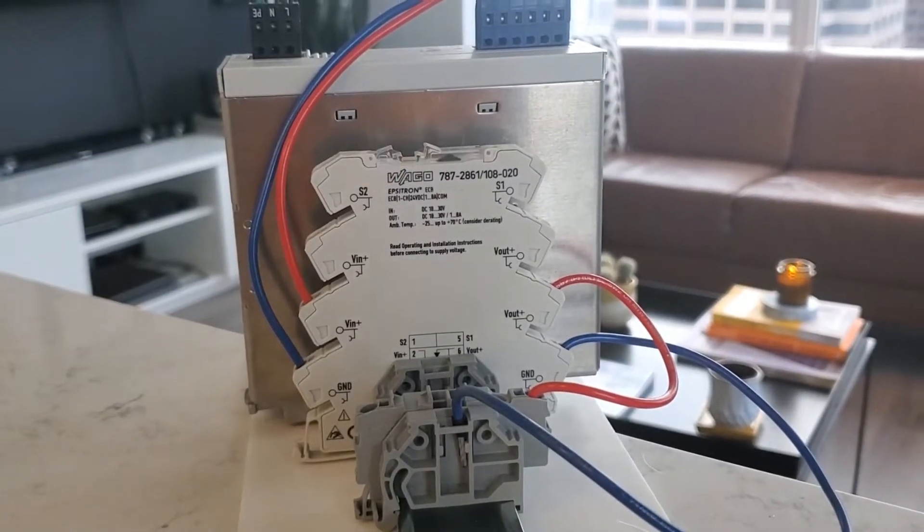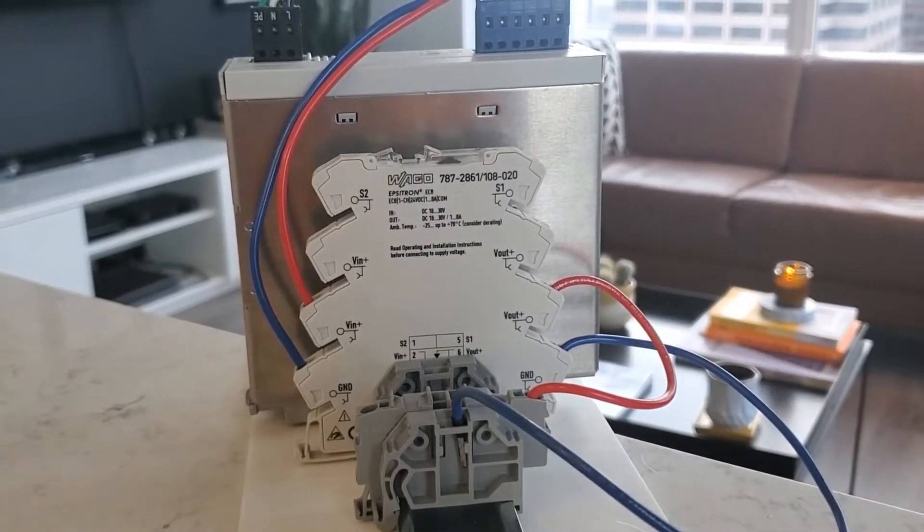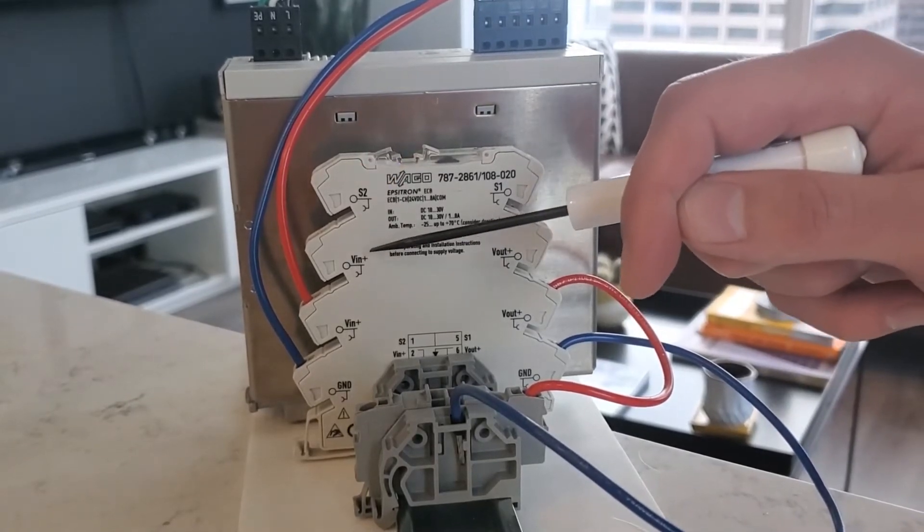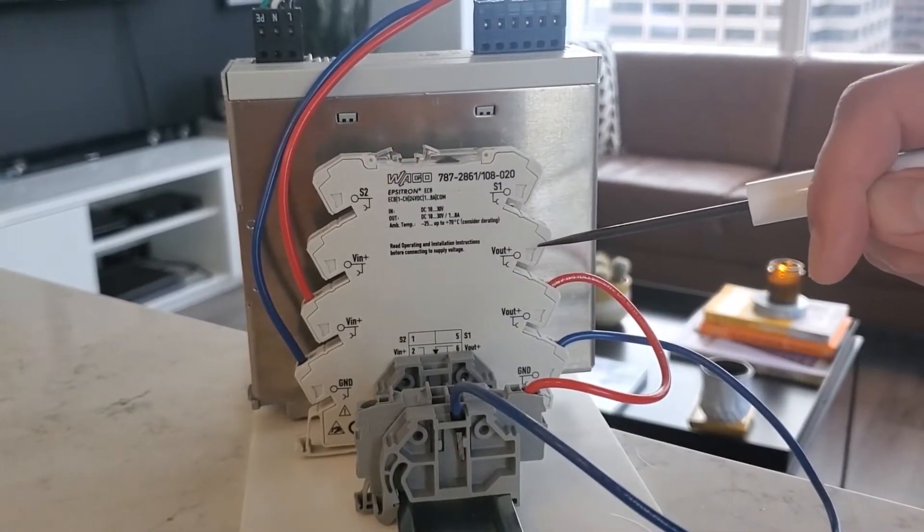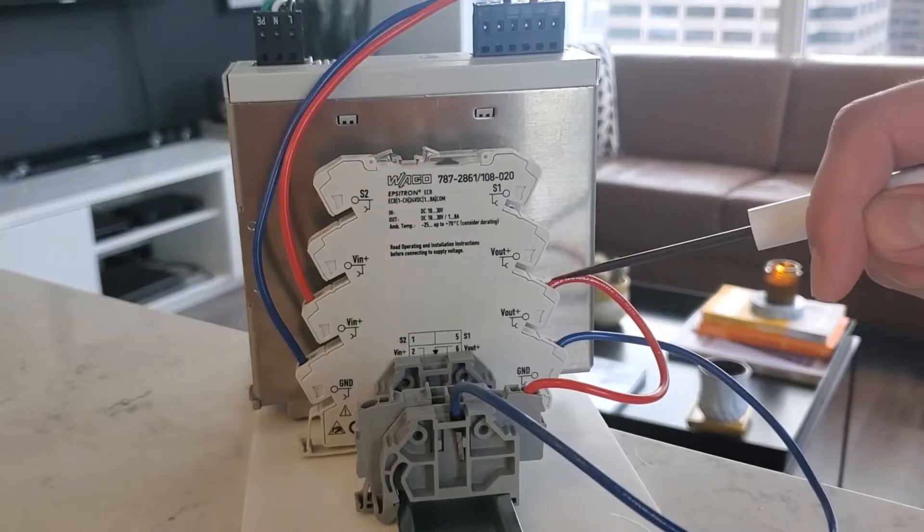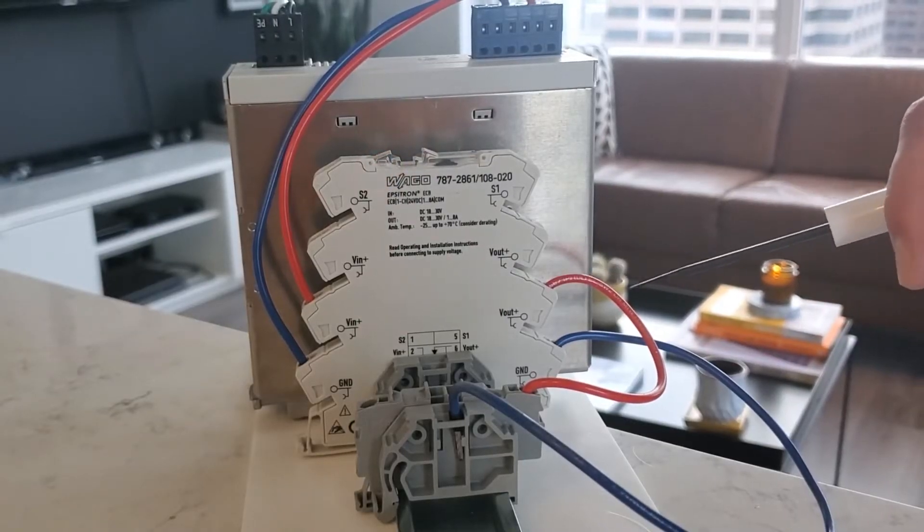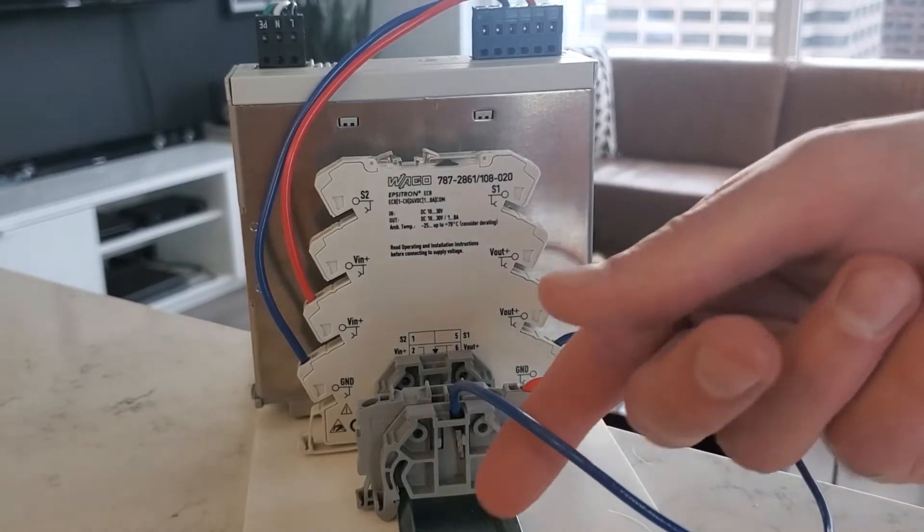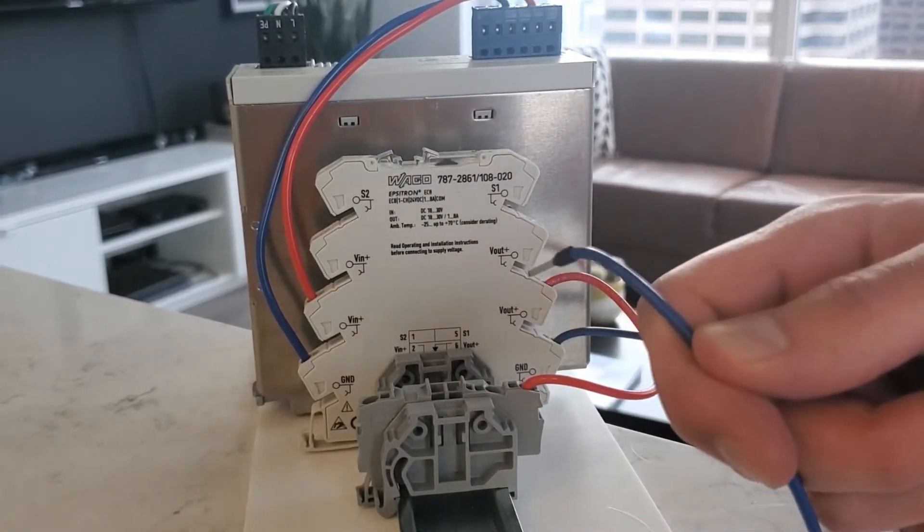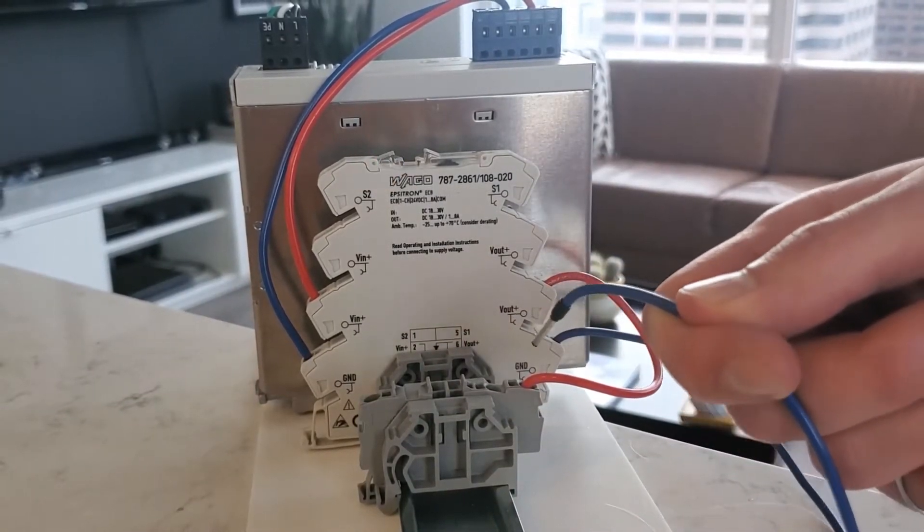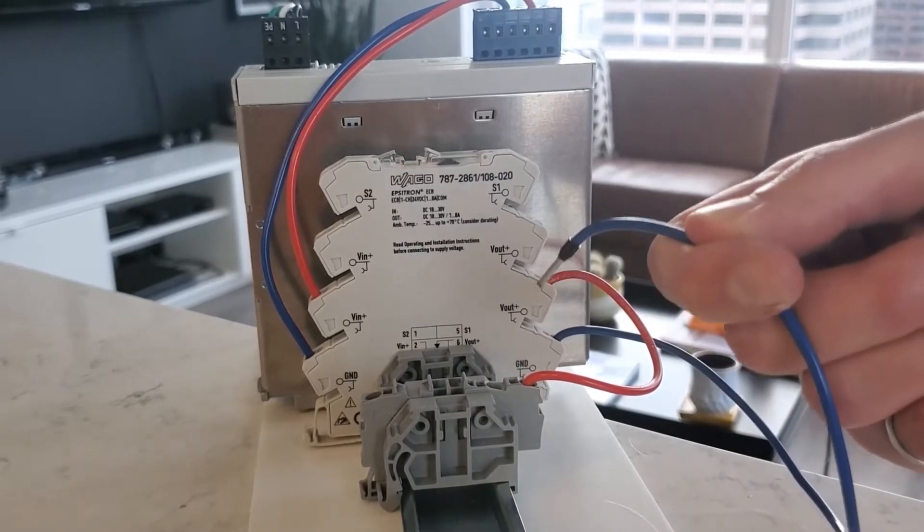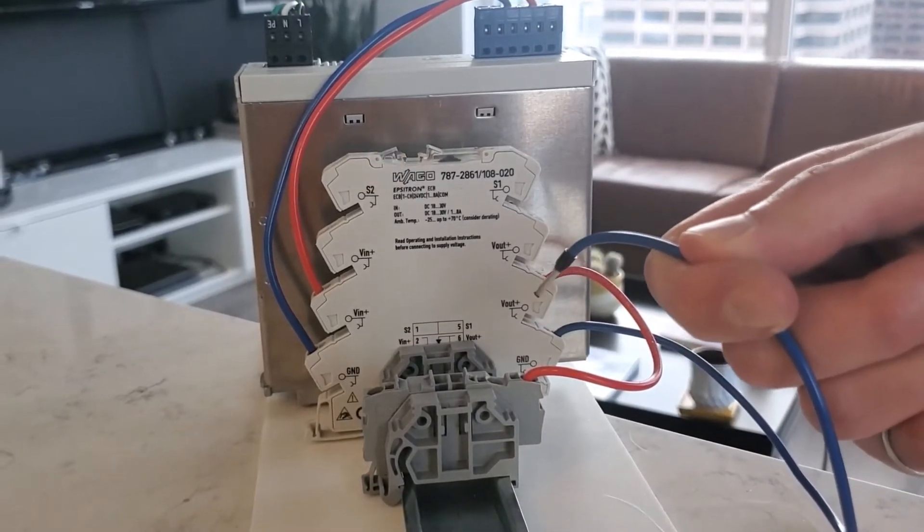If we look at how this circuit breaker is currently wired, you'll notice I have my voltage in positive and negative and my voltage out, but I only have my voltage out wired. I have my ground wired to another connection. What we're going to be doing with this demo is simulating a ground fault, so we'll be shorting the ground to the positive voltage output.